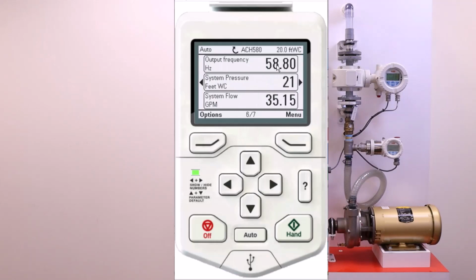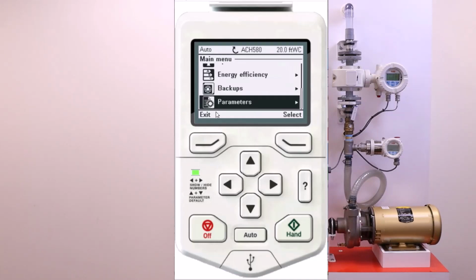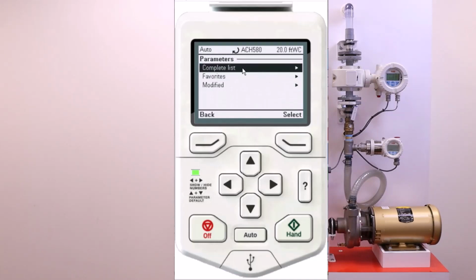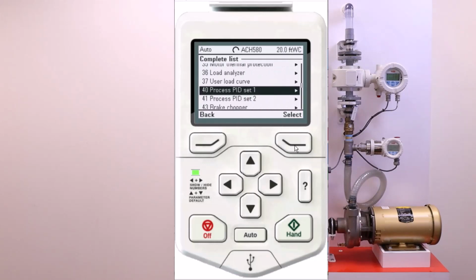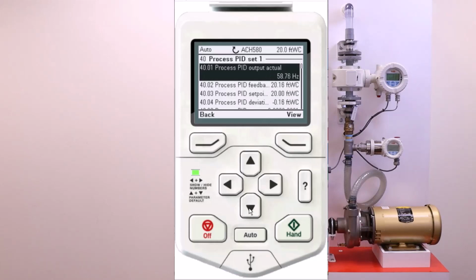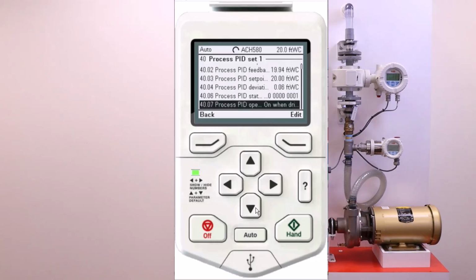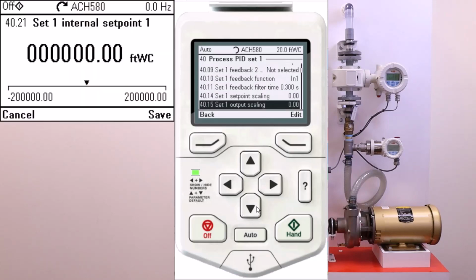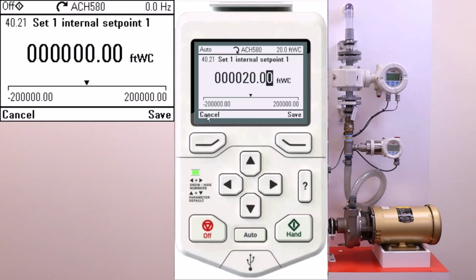35 gallons per minute. And we're set to 20 feet of water column. Let's say I want to change this, and I want to bring it down to 18 feet of water column. Now that is actually a parameter that we need to go into, because that is what we're setting up. And that is your PID set point. There's your set point. You can go to edit.